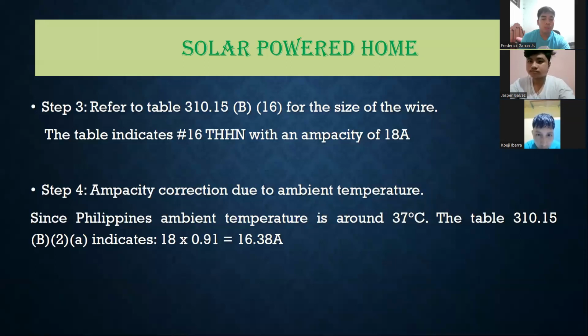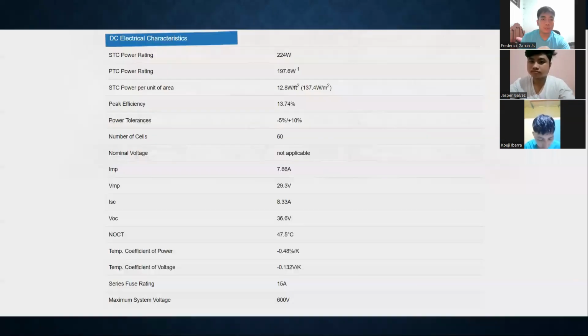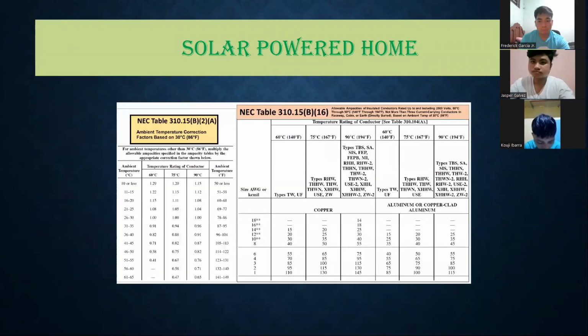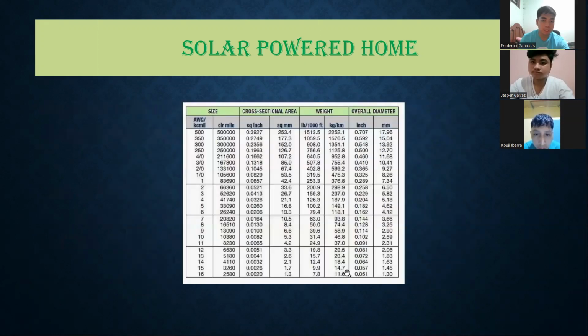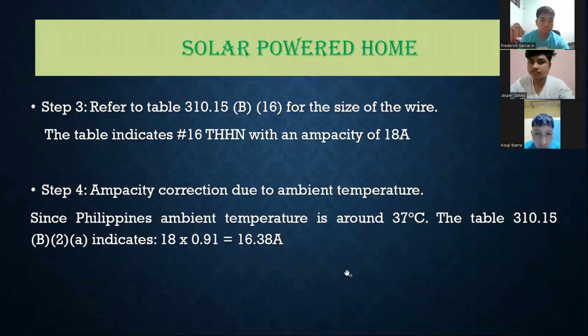Okay, so now we take a look at the table from before. Let's go back to the table. We can see for the copper, we have THHN. We have number 16, which is 18 amps. Number 16 THHN with the ampacity of 18 amps. So we'll use that for now as an estimation.